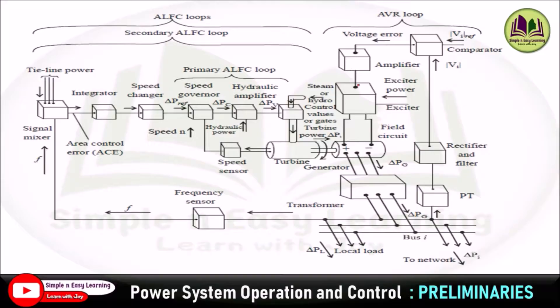We start with the primary ALFC loop, which consists of a speed sensor, speed governor, hydraulic amplifier, and finally a control valve. In the primary ALFC control loop, the speed sensor senses the speed of the turbine. This speed is compared with the reference speed, and the differential speed is sensed by the speed governor. The reference speed is compared with the actual speed from the speed sensor, and the differential speed is sent to the hydraulic amplifier. The speed governor controls speed corresponding to the differential speed by closing and opening of the control valve. If the differential speed is low, the control valve is opened so that steam flows at high speed, thereby increasing the speed of the turbine.